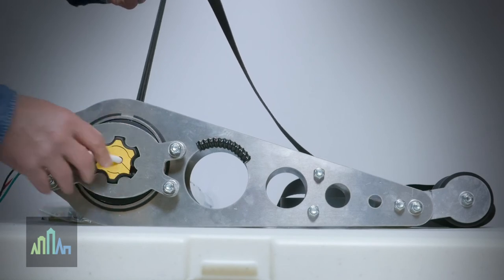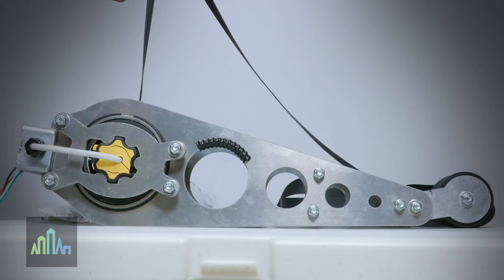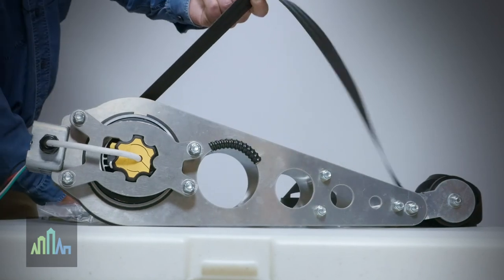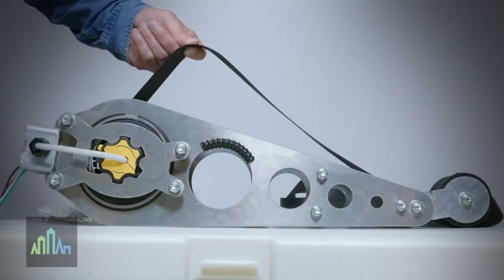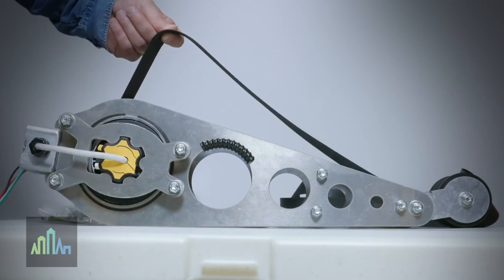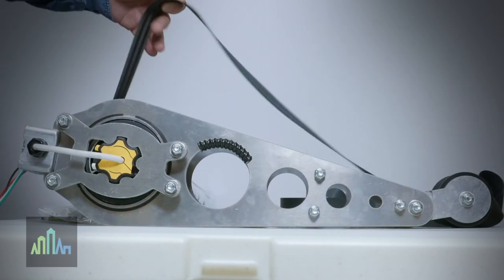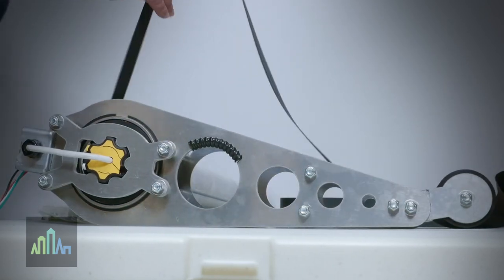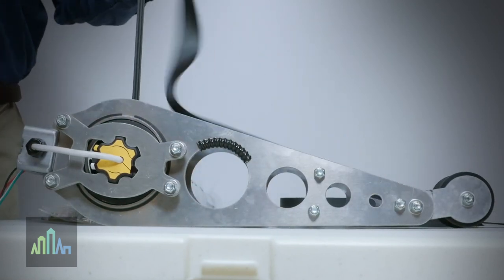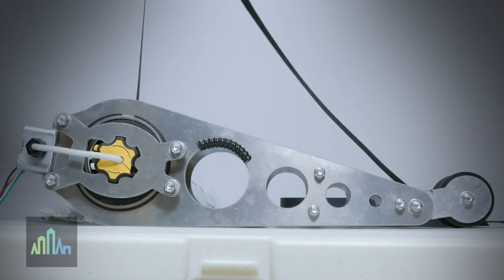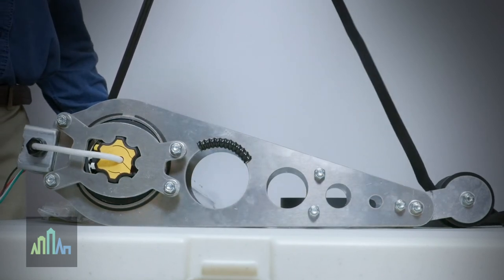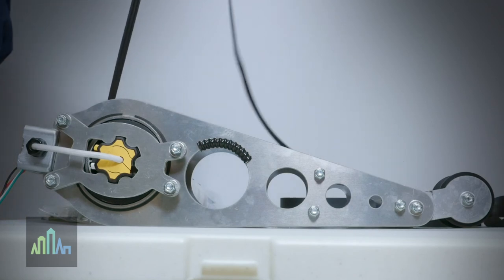I'm going to go ahead and put it back in and let's say we want one revolution. Let's say that is the up setting. Now I'm going to pop that limit switch out. Notice it stopped again at the 12 o'clock position and that gives us approximately one revolution.